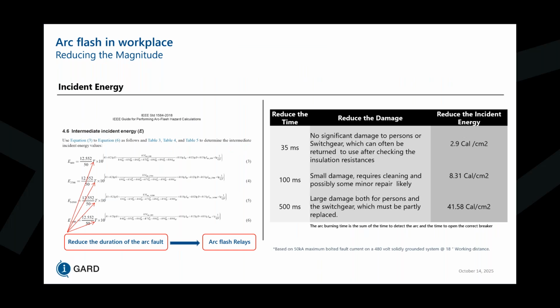In IEEE 1584, they have intermediate incident energy calculations for different voltages. You can use these to determine how much incident energy there could be in your system. The key thing is that we want to reduce the damage effect. So if we reduce the arc's buildup using arc flash relays, we can reduce the time that the arc is in the system and then try and reduce the energy effectively.